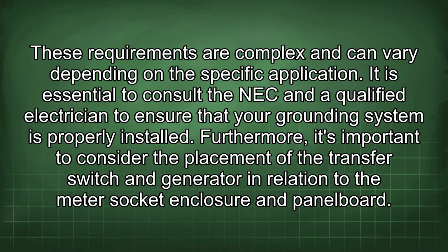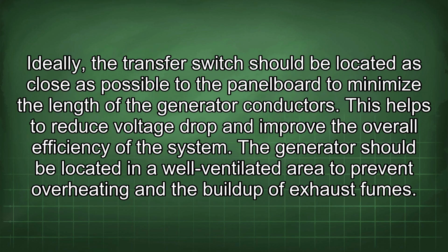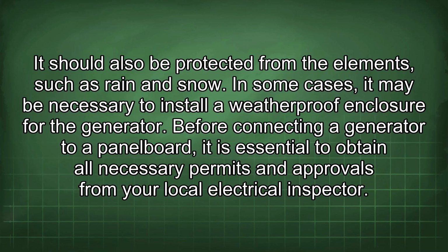Furthermore, it's important to consider the placement of the transfer switch and generator in relation to the meter socket, enclosure, and panel board. Ideally, the transfer switch should be located as close as possible to the panel board to minimize the length of the generator conductors. This helps to reduce voltage drop and improve the overall efficiency of the system. The generator should be located in a well-ventilated area to prevent overheating and the buildup of exhaust fumes. It should also be protected from the elements such as rain and snow. In some cases, it may be necessary to install a weatherproof enclosure for the generator.